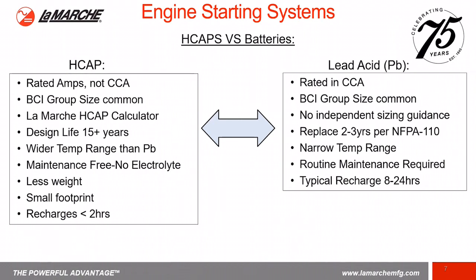The design life on the hybrid capacitor is well over 15 years, while the lead acid type batteries are around 2 to 3 years, maybe a little bit longer, but NFPA recommends that you replace your genset batteries every 2 to 3 years. The HCAPs provide a wide range of temperature, while with lead acids, the optimal temperature is 77 degrees F. With the HCAPs, there is no maintenance required.